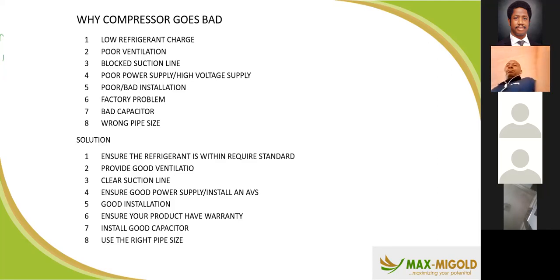Every AC and size have their pipe sizes, the suction line and liquid line. If you don't use the required pipe, you underuse the AC or overuse it. Understand? Then possible solutions: ensure refrigerant is within required standard, provide good ventilation, clear suction line, ensure good power supply, good installation, ensure your product has warranty, install a good capacitor, then use the right pipe size.